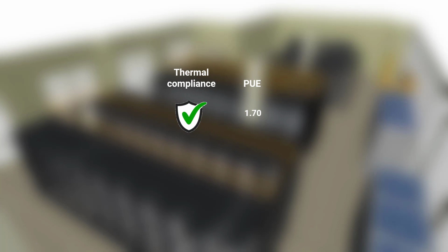This approach eliminated the compliance problem, but at the cost of a higher PUE. That was the result of having to supply more air and reduce the supply air temperature. And this highlights the challenge. The inability to visualize airflow and cooling system operation makes it difficult to balance compliance and efficiency, which puts cooling system performance at risk.